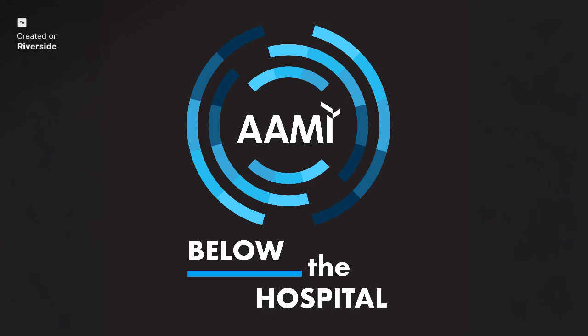Is there anything else? Yes, they definitely put down that for ventilation and exhaust systems for these sterilizers, you have to have a minimum of 10 total air exchanges per hour, right? Now that is written in there. Another thing to look for, at least for ETO, is the EPA sterilization regulations for monitoring programs. That has been updated. What kind of monitoring programs, and how long do you have to do these programs? How long you have to keep records has been updated as well, as per EPA.